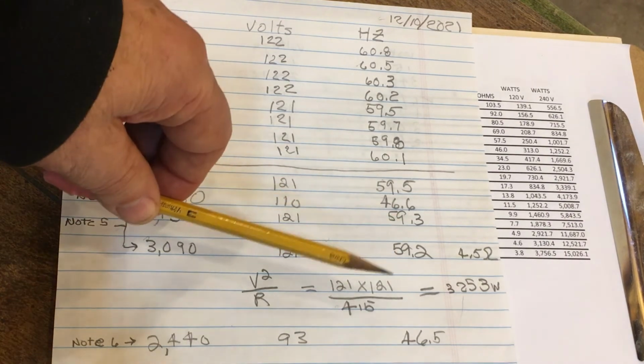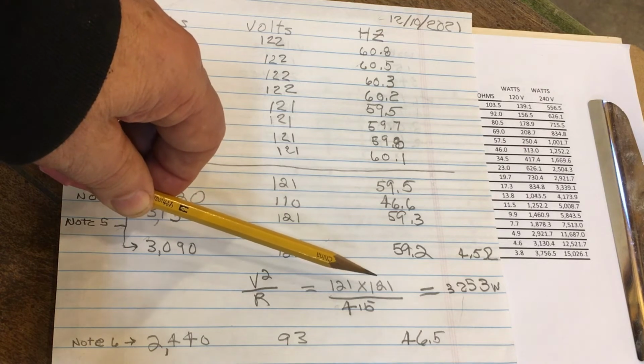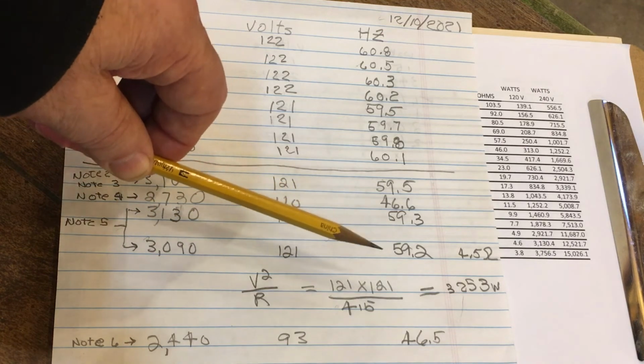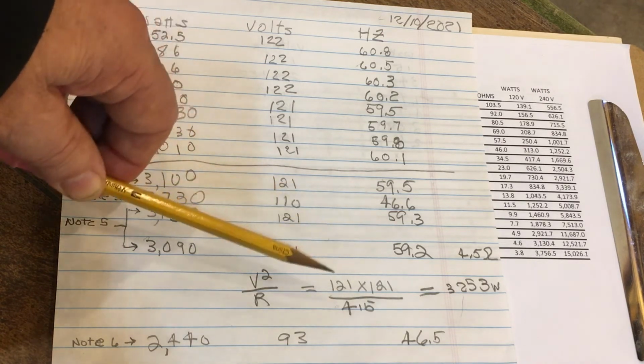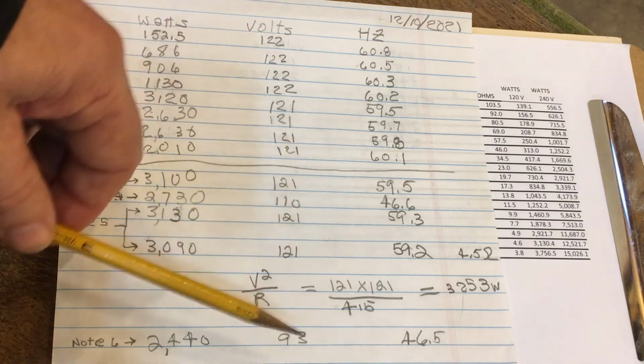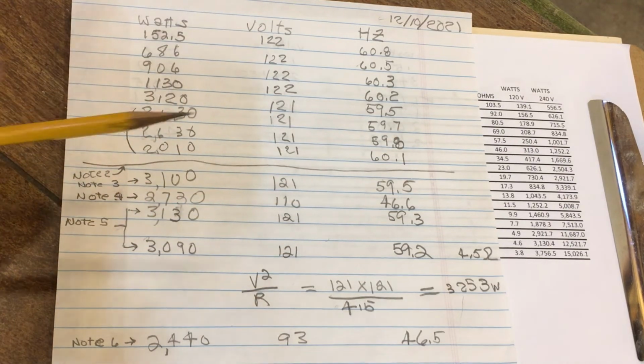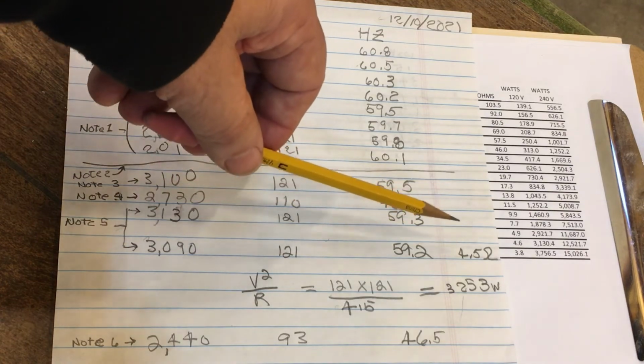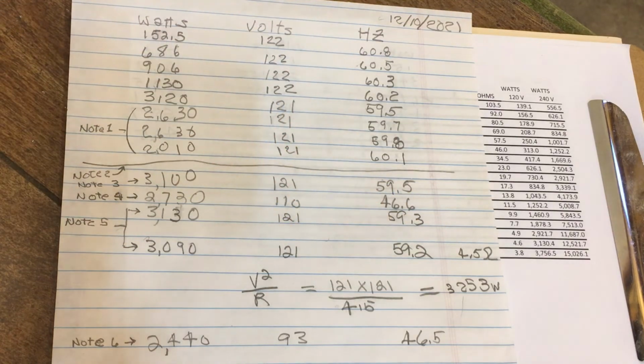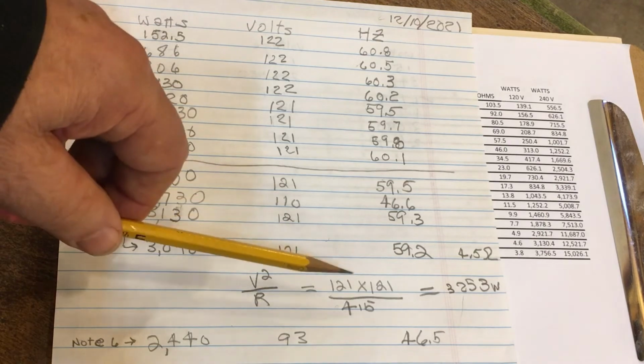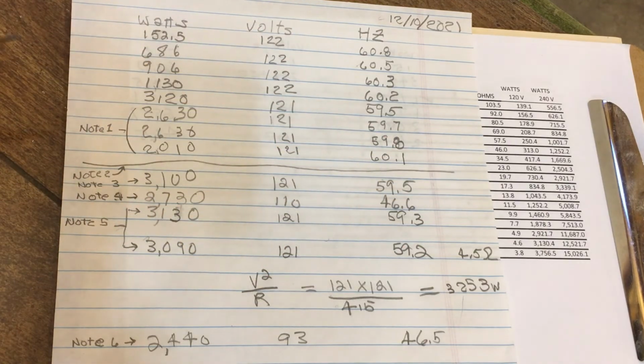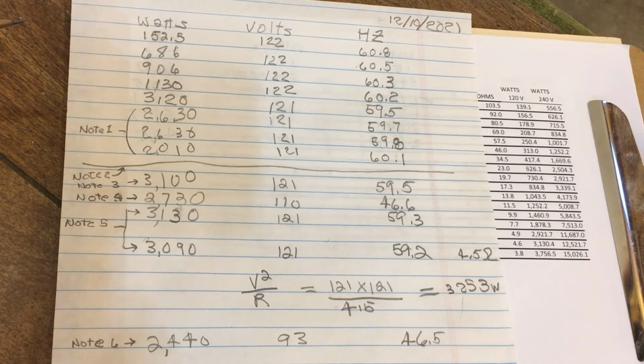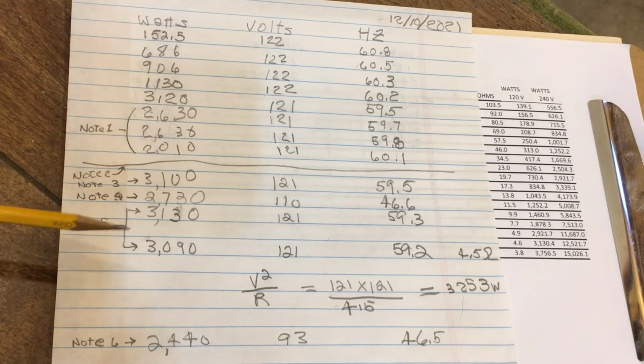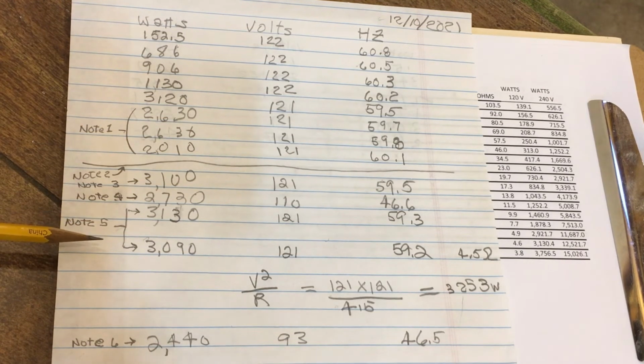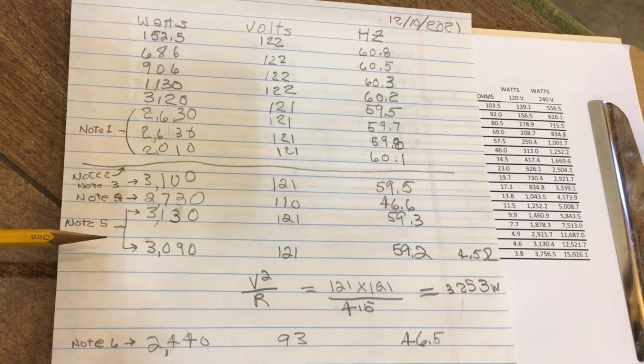But also we know that as soon as I took the power off of the unit, the resistors would cool off slightly in the heating elements, and it may have shifted the ohms. And also when I get down to, say, below 10 ohms, my ohm meter can give varied results sometimes. It's very hard to get good accurate readings, but I have some faith that around 3,000, 3,100 is probably about the best we were doing here.